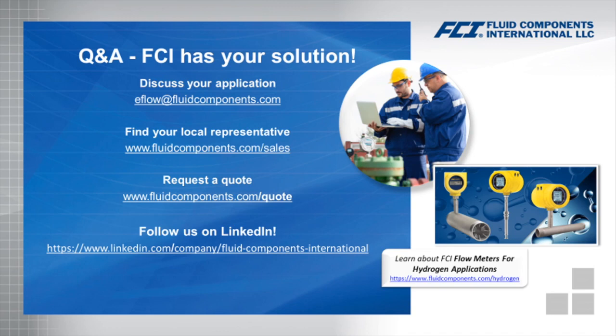This person is asking, how is high velocity of H2 as process fluid considered during calibration? Are the present calibration facilities H2 ready? That's a great question because, again, it's one of those things you really got to look at when dealing with manufacturers and the calibration of any type of flow meter for hydrogen.